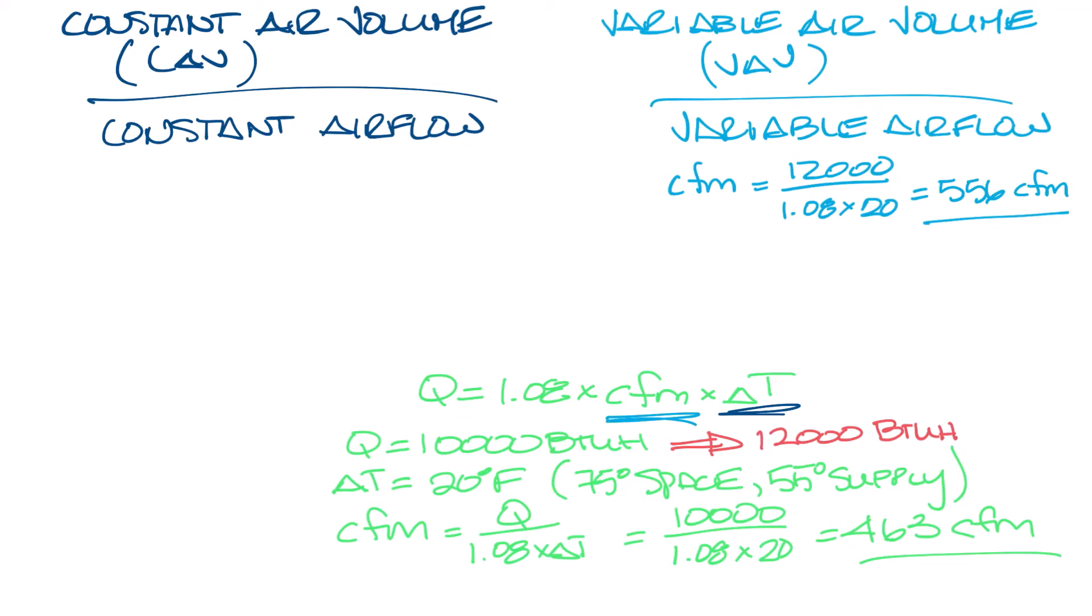So now let's look at the constant air volume system. In this system, the airflow is constant, so the CFM is still 463. So we need to calculate the delta T to handle the load, which is 12,000 divided by 1.08 times 463, and that equals 24 degrees Fahrenheit. So if we want to have a space that is 75 degrees, then a 24 degree delta T means our supply air is 51 degrees Fahrenheit.